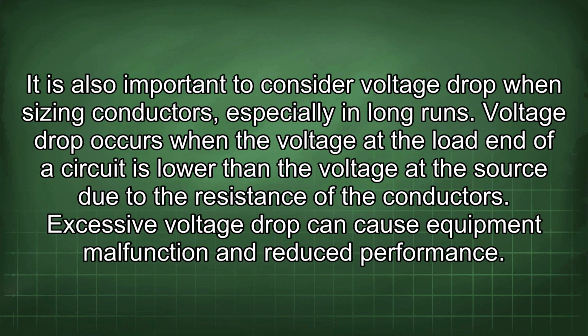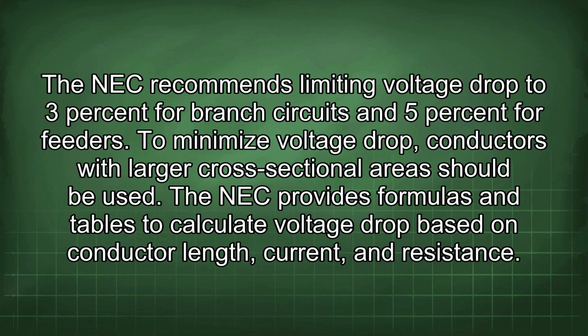It is also important to consider voltage drop when sizing conductors, especially in long runs. Voltage drop occurs when the voltage at the load end of a circuit is lower than the voltage at the source due to the resistance of the conductors. Excessive voltage drop can cause equipment malfunction and reduce performance. The NEC recommends limiting voltage drop to 3% for branch circuits and 5% for feeders. To minimize voltage drop, conductors with larger cross-sectional areas should be used. The NEC provides formulas and tables to calculate voltage drop based on conductor length, current, and resistance.